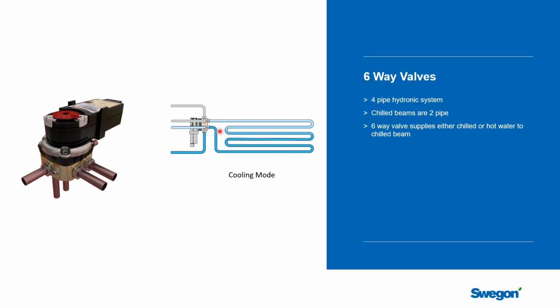And that improves the capacity of the beam because you're not splitting the coil 1/3 heating, 2/3 cooling. It helps you a bit in cooling, gives you a little bit more capacity. It makes a significant increase in the capacity of the beam in heating because you got a lot more tubes that can add heat, which is why it's really popular in hotels and in dormitories and single room applications where you're going to use chill beams in a residential application. So we can see this in cooling. Let's just switch over. Now you see it in heating. The valve has moved its position and has connected the coil to the hot water loop that's in the building. And so now you can see that the hot water will flow out through the coil. Every tube in that coil is adding heat, so you get a lot more capacity.